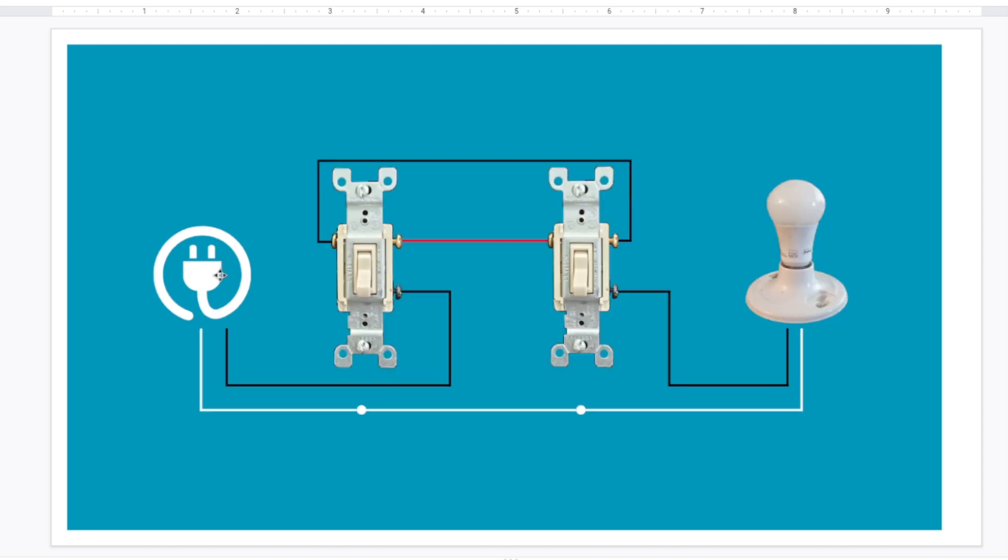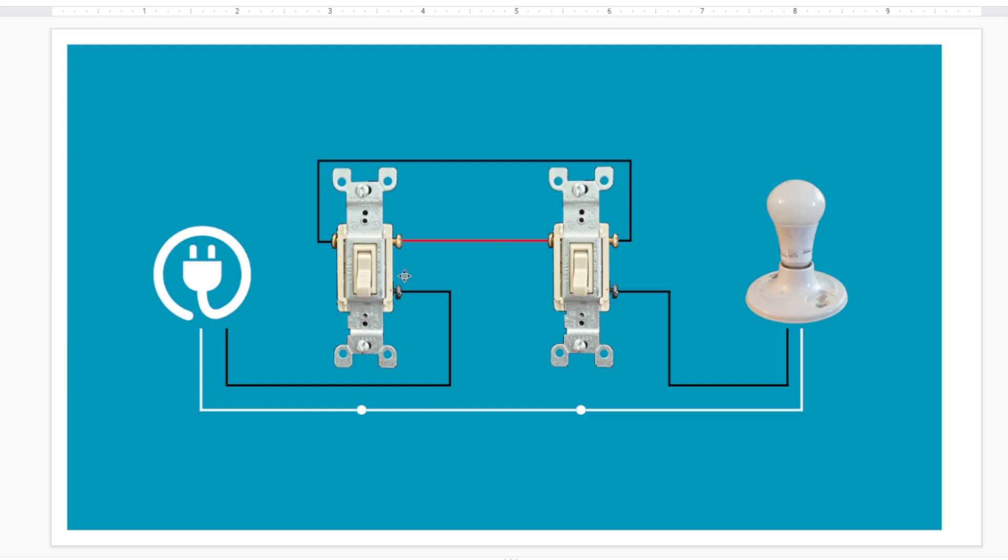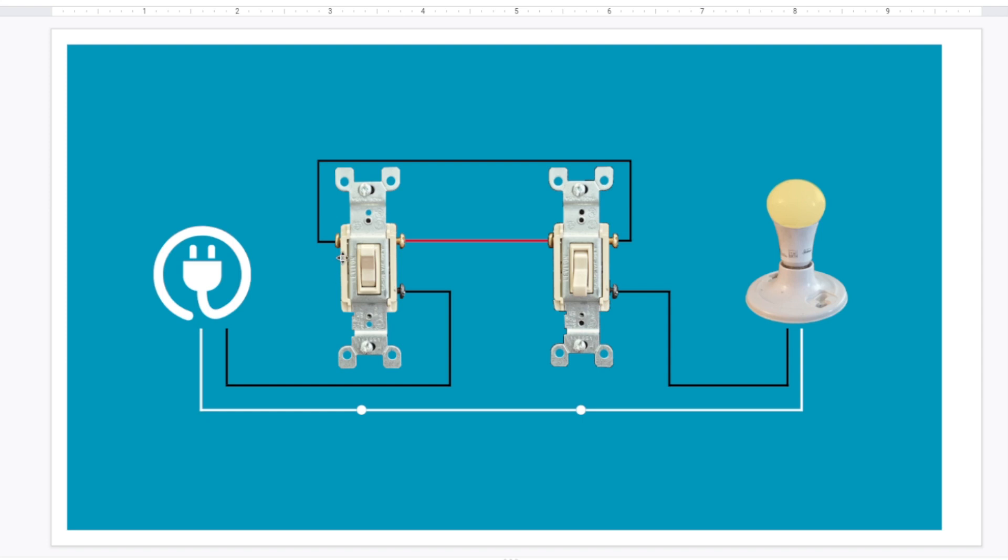So typically a three-way switch, you have your power coming into your light switch, your first light switch. And from there, the line power gets put onto this common terminal. And it's common between these two, what they're called travelers. And that passes power to the next switch depending on the configuration of the switches in the up and down position. And finally, it comes out of the common terminal on the other three-way out to your lamp. And if you were to change one of the light switches, power would then turn on your lamp.